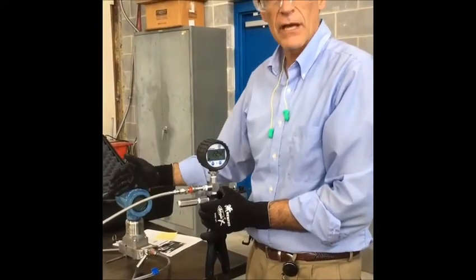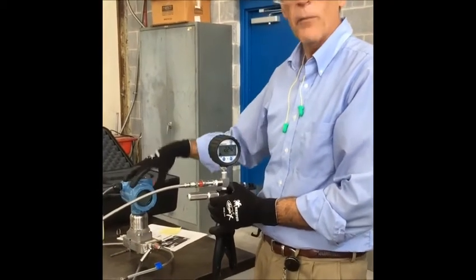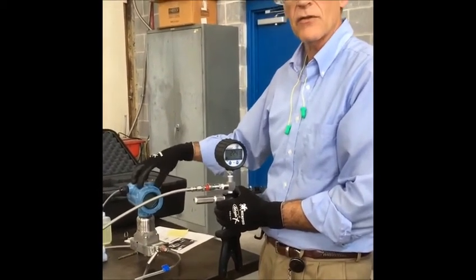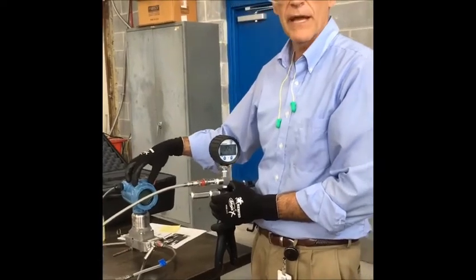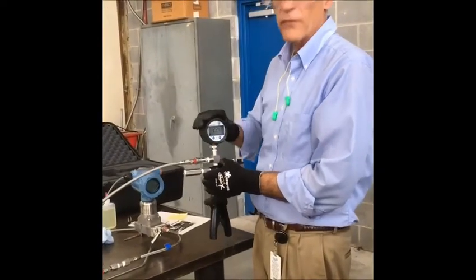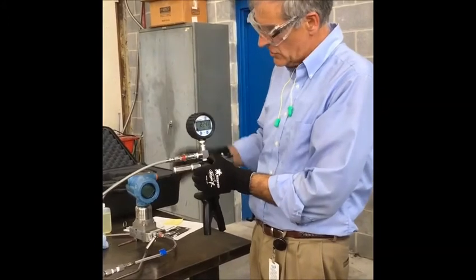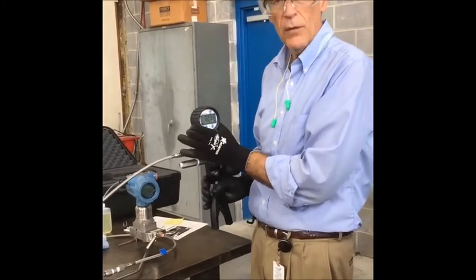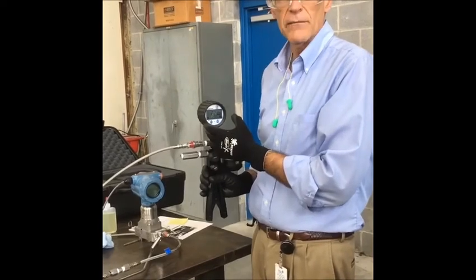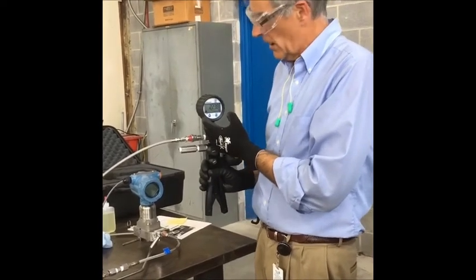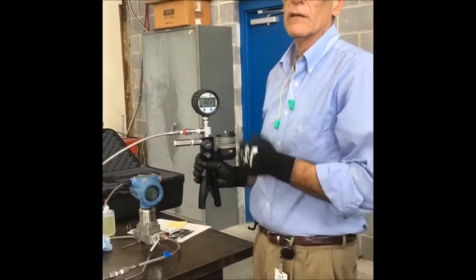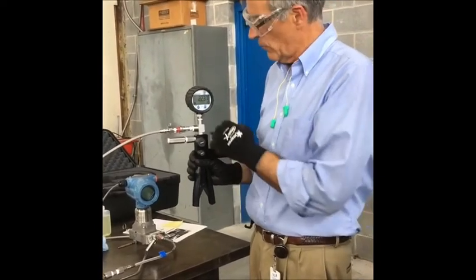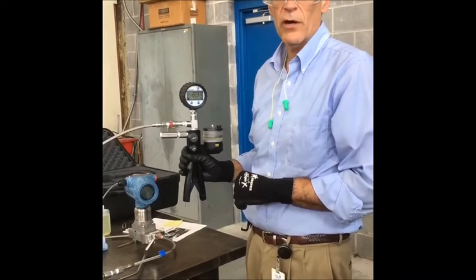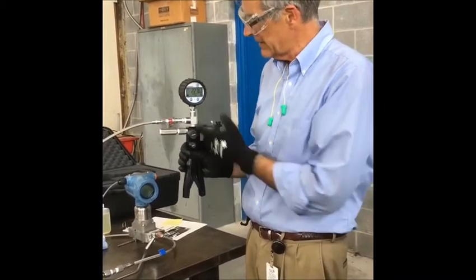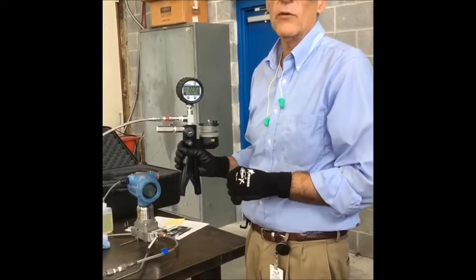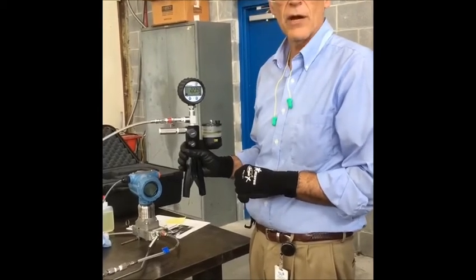If it doesn't cut out, then you've got work to do on your control panel to make sure this high pressure cutout is set correctly, or to recalibrate it in the panel so that it is in calibration with your master gauge. It's important that the gauge used on the calibration pump be calibrated to a NIST standard gauge. We use a dead weight tester here in the lab. It's traceable to NIST, so we set the calibration just before we start. In an operating plant, you would probably need to send your gauge out and get it calibrated maybe once a year and keep records of the calibration.